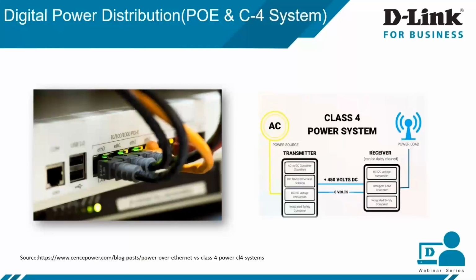Let's focus on some differences between power over Ethernet and the class 4 fault managed system - both are DC power distribution systems. PoE circuits are limited to 100 watt maximum and 60 volt maximum. Everybody must be aware that whatever is below 60 volt DC is called safety extra low voltage, or low voltage. So whenever I talk about a PoE switch, all the ports are safety extra low voltage.